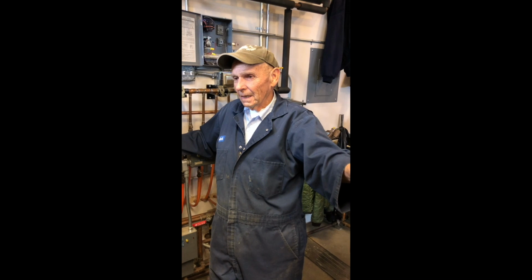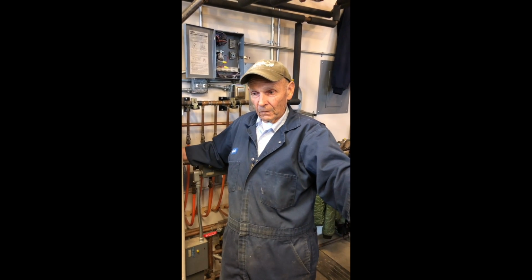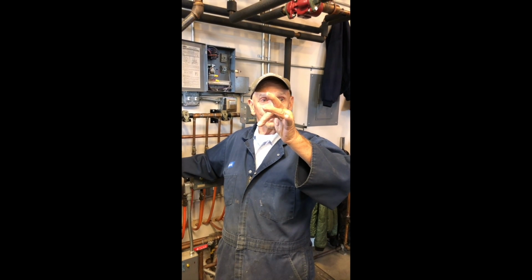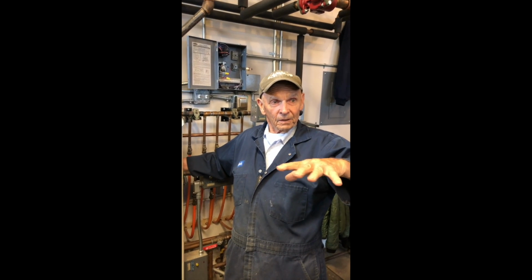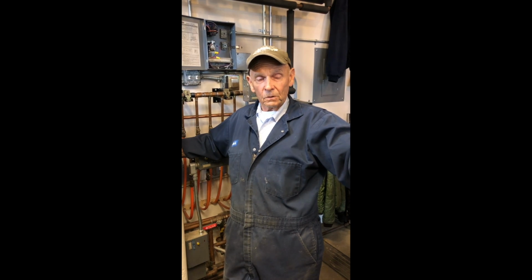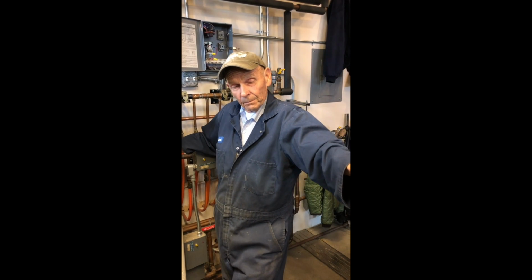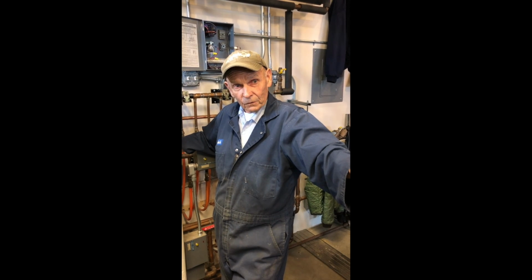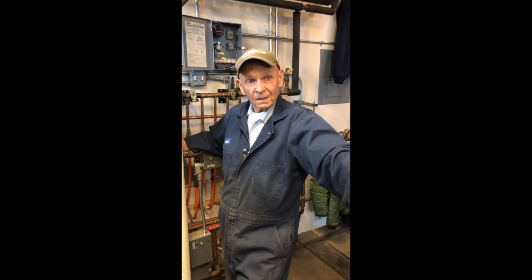So the normal cycle is that the fan comes on, it's calling for heat again, the boiler's hot but it's cooled down, so the fan comes on first, then the damper to let air into the combustion chamber opens. As soon as that happens, the fire comes alive and the coals get red hot and they light the wood and you're back on a heating system. The hazard is to open it up when it's just shut off, and you can ignite those fumes.